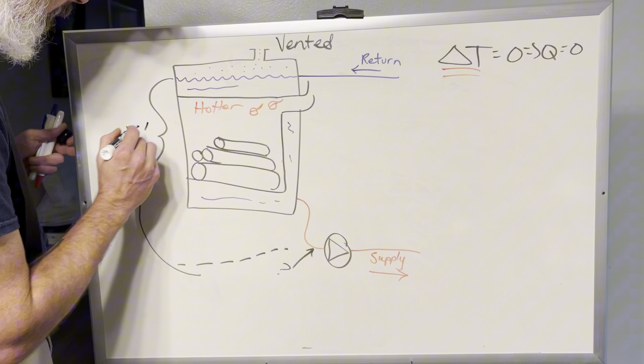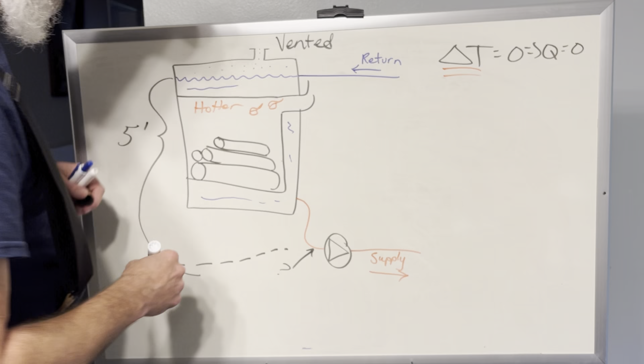Let's say this is 5 feet. The suction side of that pump, the most it can ever see is 5 feet of head at the suction. Depending on your runs, your runouts going like this, you may have to go a really long way, and that's fine. You get big pumps, bigger pipe. You can pump miles and miles. We do that all the time with large campuses. You have a utility plant somewhere, and you'll pump the water a long way away, to college campuses.